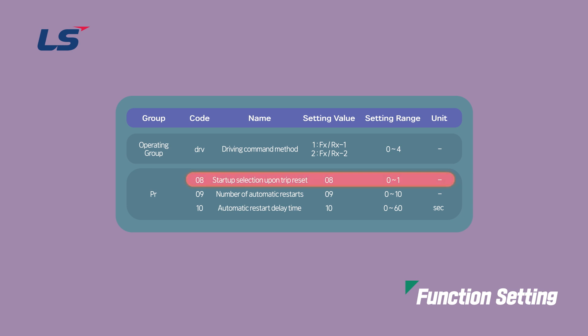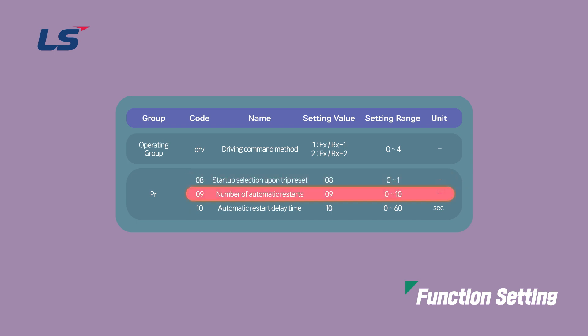Enable the Reset and Restart feature by setting the PR Group 8 parameter to YES. Set the number of Reset Start attempts in the PR Group 9 parameter, and set the Restart delay time in the PR Group 10 parameter.